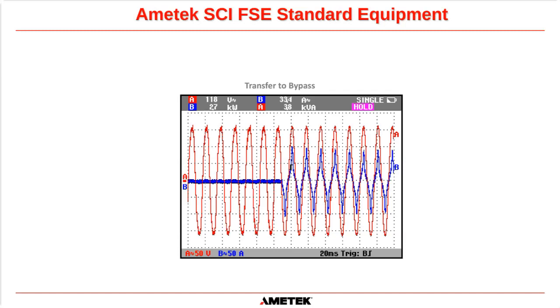And then I mentioned earlier with our oscilloscopes that we capture the exact transfer point between inverter to bypass and bypass back to inverter. And how we do that is we put an amp clamp on the output of the system. In this circumstance, if we're transferring to bypass, we will put the amp clamp on the bypass supply. So in normal operation, which is this portion here, we should have no current flowing through the bypass amp clamp because we're on inverter. But as soon as the amp clamp sees current flowing through it, that means there is current flowing through the bypass, we know that that is the exact point somewhere between here and here where the system transferred from inverter to bypass.